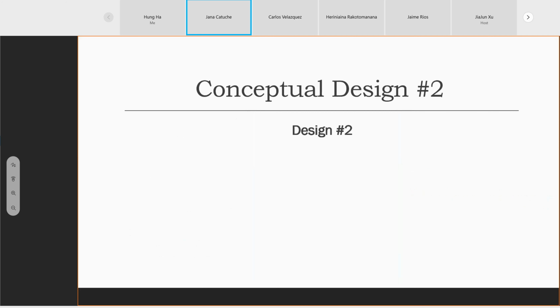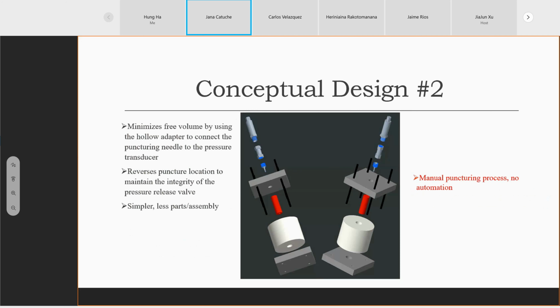For our second conceptual design, this is the exploded view. It is very similar to the first and also the existing design. The main difference you can see here would be the coupling. This coupler is pretty much a hollow adapter that would connect the puncturing needle as well as the pressure transducer. So this would minimize the majority of the free volume that we would get from adding that pressure transducer to the puncturing needle. Here in the battery in red, you can see the tip.